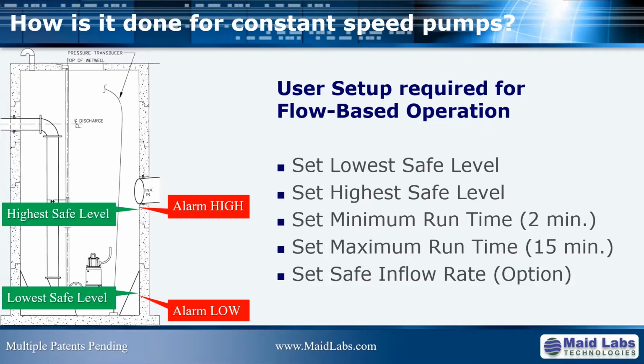Then you need to specify what is an acceptable minimum run time that you think would be acceptable for your pumps to run, and what is the maximum before you would like to switch to another pump running. And you can also specify what you consider a safe flow rate coming in. So when the flow rate is above that value, you should run the pump low in the well. When the flow rate coming in is lower than that value, then you can run the pumps high.